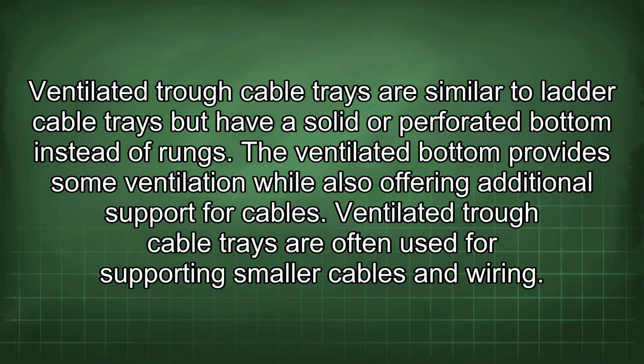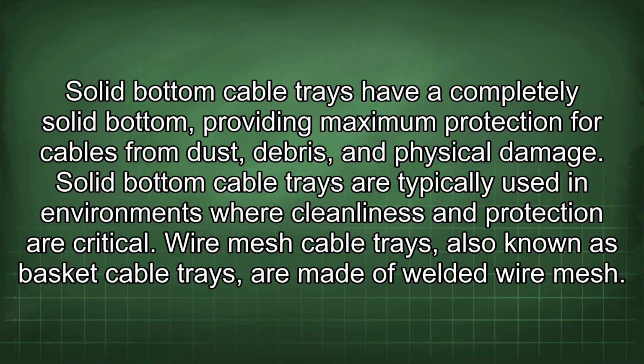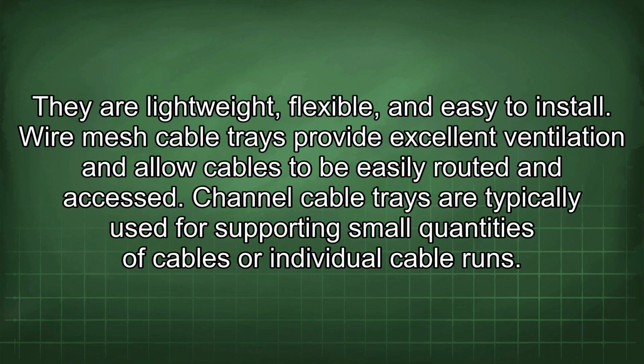cables and wiring. Solid bottom cable trays have a completely solid bottom, providing maximum protection for cables from dust, debris, and physical damage. Solid bottom cable trays are typically used in environments where cleanliness and protection are critical. Wire mesh cable trays, also known as basket cable trays, are made of welded wire mesh. They are lightweight, flexible, and easy to install. Wire mesh cable trays provide excellent ventilation and allow cables to be easily routed and accessed.